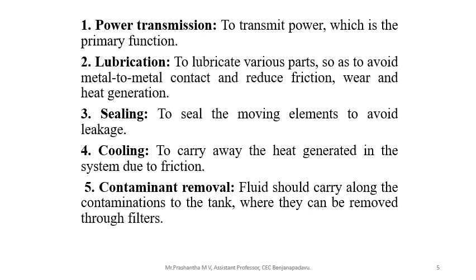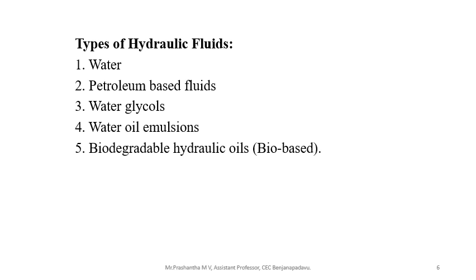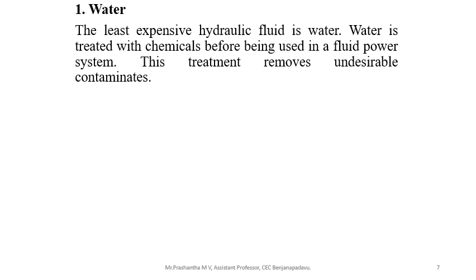Next, types of hydraulic fluids. As you know already, water, petroleum based fluids, water glycols, water oil emulsions, biodegradable hydraulic oils. First one, water. Water is abundant in nature and it is least expensive, so water is commonly used as a hydraulic fluid. And water has many disadvantages. It does not have many desirable properties of the remaining hydraulic fluids. It has very poor rust and corrosion resistance, poor lubrication properties, poor thermal stability, poor operational efficiency, and a low viscosity. Water corrodes the metallic parts. So these are some disadvantages, and water is less used nowadays compared to other hydraulic fluids.